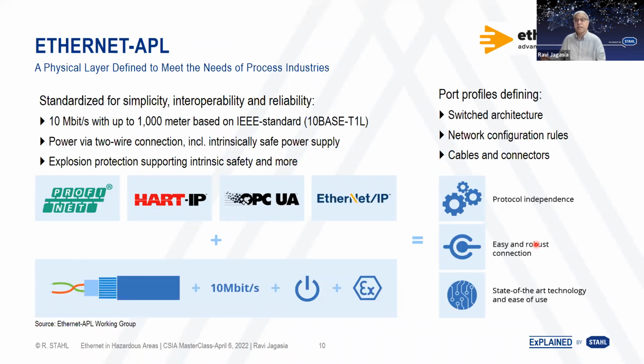They wanted to ensure that it would be minimum 10 Mbps data, able to travel a long distance, able to work with an IEEE standard, so that we don't need to develop a new Ethernet standard. Definitely it has to be two-wire, ideally with intrinsic safety built in, and then interconnections. You needed to be sure that you could connect all these protocols from these standard development organizations onto the standard cable at a standard rate with an intrinsically safe power supply, and ensure it is hazardous area suitable.